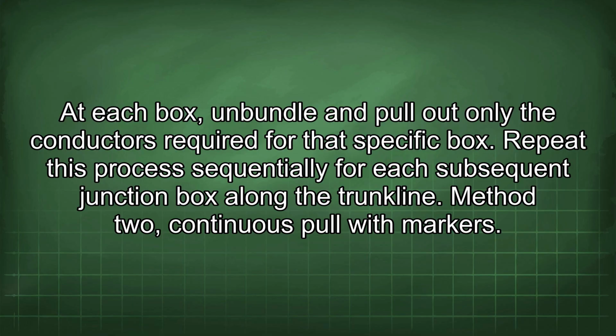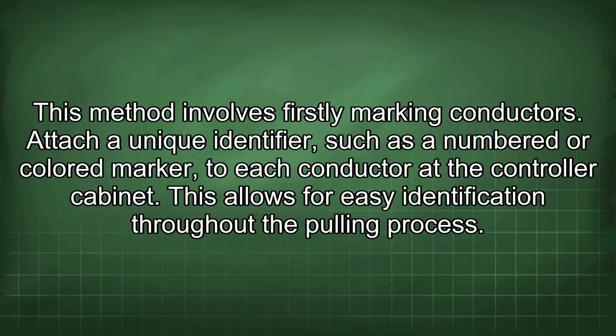Method 2. Continuous pull with markers. This method involves firstly marking conductors. Attach a unique identifier, such as a numbered or colored marker, to each conductor at the controller cabinet. This allows for easy identification throughout the pulling process.